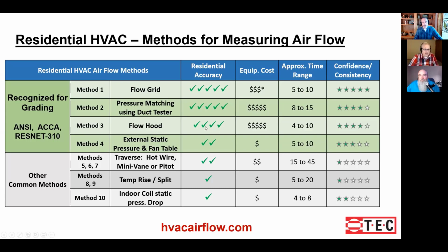Depending on the situation, you might need 2 flow hoods, one for the larger flows on a single return filter grill system, and then you might need a smaller hood to measure multiple return systems. And then method 4 is the external static pressure and the fan table. This is what Ed's talking about. This is a really common method, and it's sort of a workhorse. A lot of people that get into airflow start here, and it's a good way to do it as long as you can verify that the equipment is more or less in the same condition it left the factory.